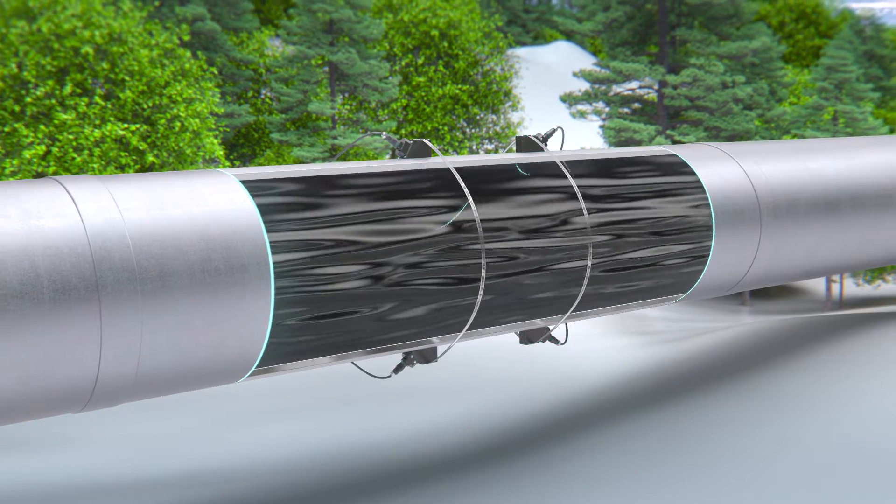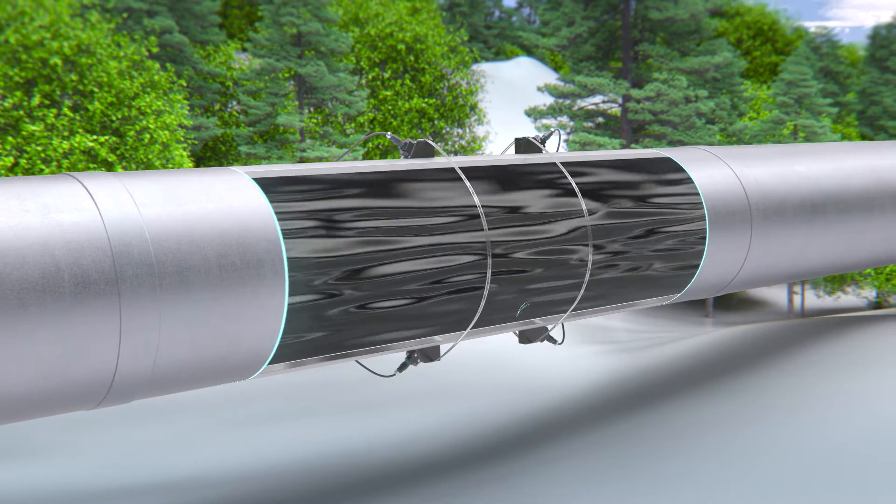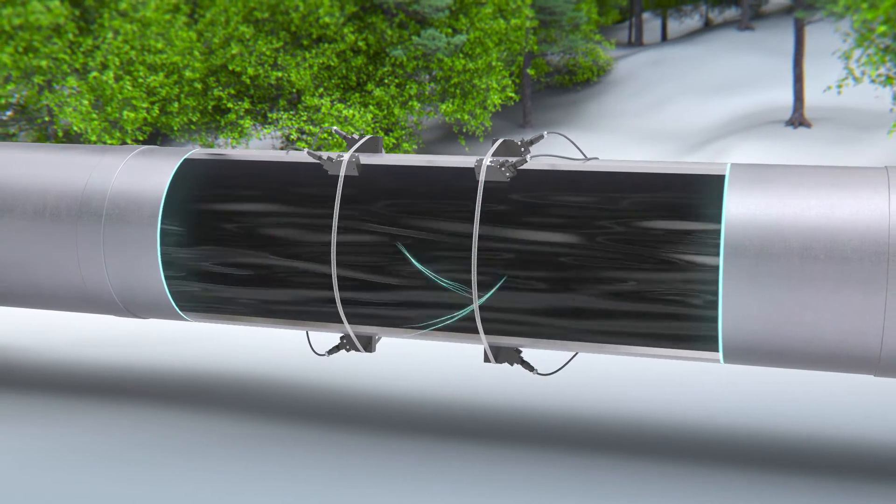Default settings always include two paths. However, four pairs of sensors per tube can be used in sections with critical flow.